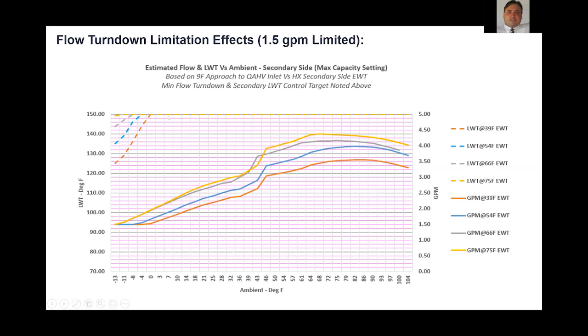And that's what these dashed lines are indicating. You can see here that if you are limited with flow turn down to that 1.5 GPM level, once you start getting below 0 degrees, minus 4 roughly, you start to lose control of discharge water temperature going to your tank.